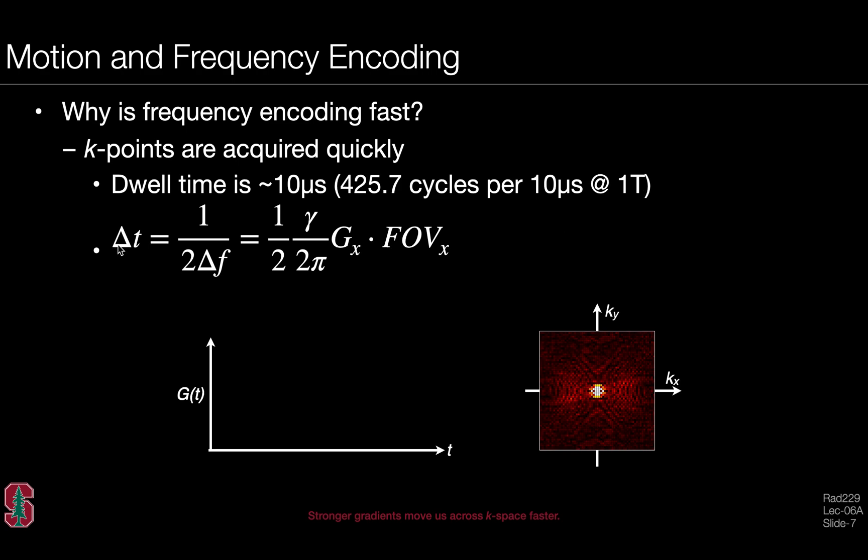Once we pick a dwell time, or in fact, we might pick the readout bandwidth instead in terms of frequency, that leads us to design the gradient amplitude that we need for a particular field of view. The gradient amplitude is directly related to our dwell time. Stronger gradients will allow us to dwell for shorter periods of time, and slow gradients will have us dwelling for longer periods. Depending on how we've designed our gradient waveform, we will move quickly or slowly across K-space. Stronger gradients move us across K-space even faster. But if we move across K-space very fast, we also have fewer cycles of precession during every K-point acquisition, and this contributes to lower signal-to-noise.